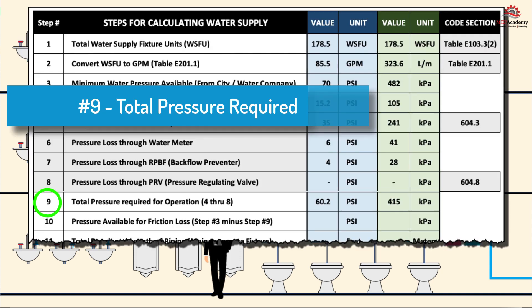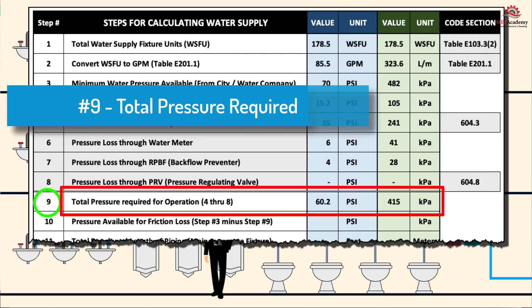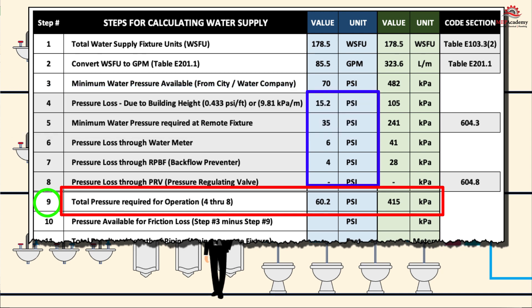Step 9: Total Pressure Required for Operation. Add up all pressure losses and the required minimum water pressure at the remote fixture with the highest requirements. Adding steps 4 through 8 in our example equals 60.2 PSI or 415 kPa. This is the total pressure required for proper operation, not including the pressure drop caused by water flowing through pipe and fittings.